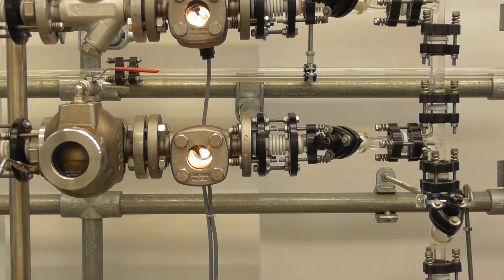Steam lock can easily be prevented by locating the steam trap closer at the heat exchanger, by changing the flow direction from horizontal to vertical flow, or by installing a balancing line from the steam trap to the condensate outlet of the heat exchanger.